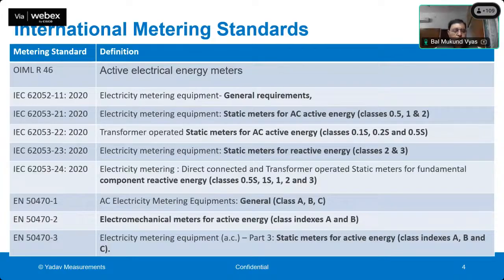If we talk about European requirements, in Europe, electricity meters also mandatorily have to be tested as per the Measuring Instruments Directive, and they have to be tested as per EN 50470-1, -2, or -3 standards. These have slightly different accuracy classes, which are called class A, class B, and class C, similar to class 1, class 2, and 0.5.